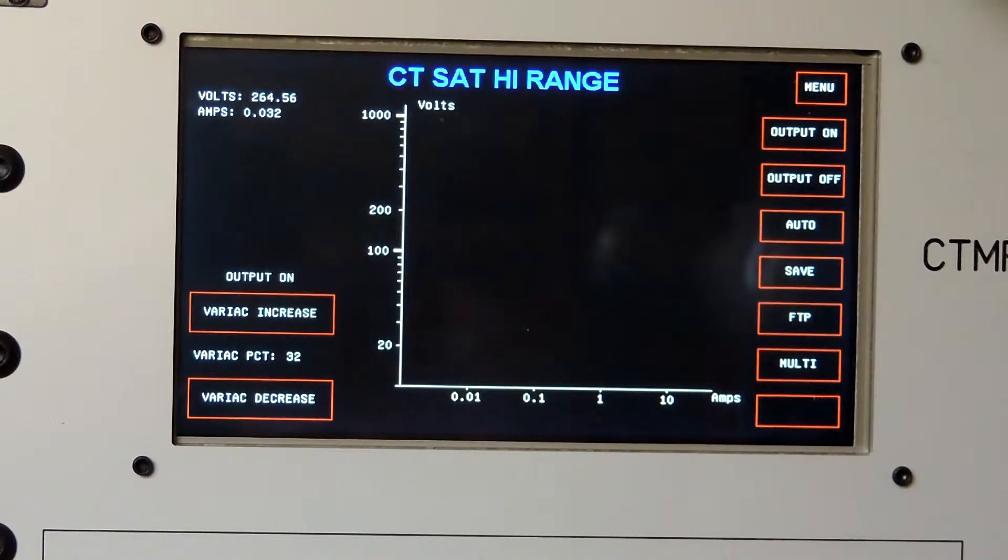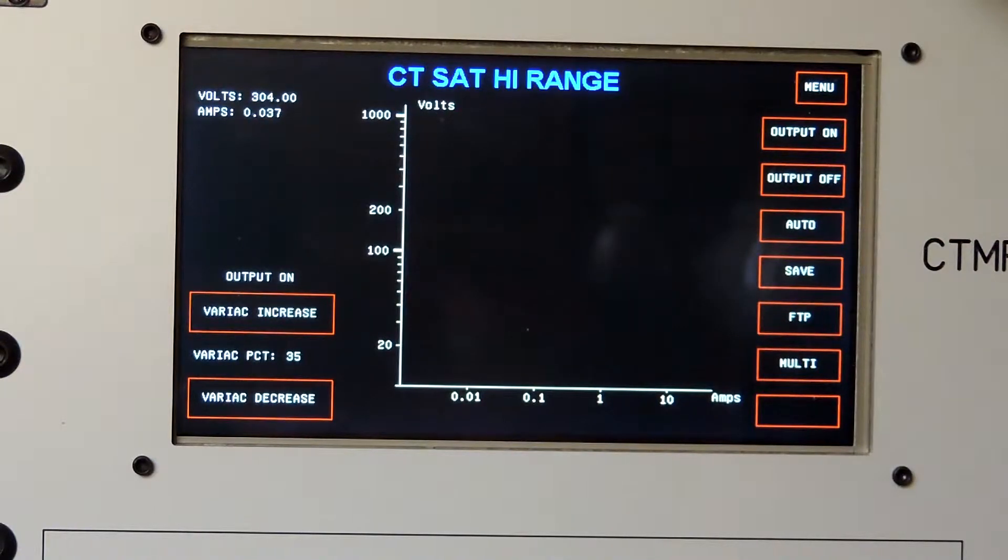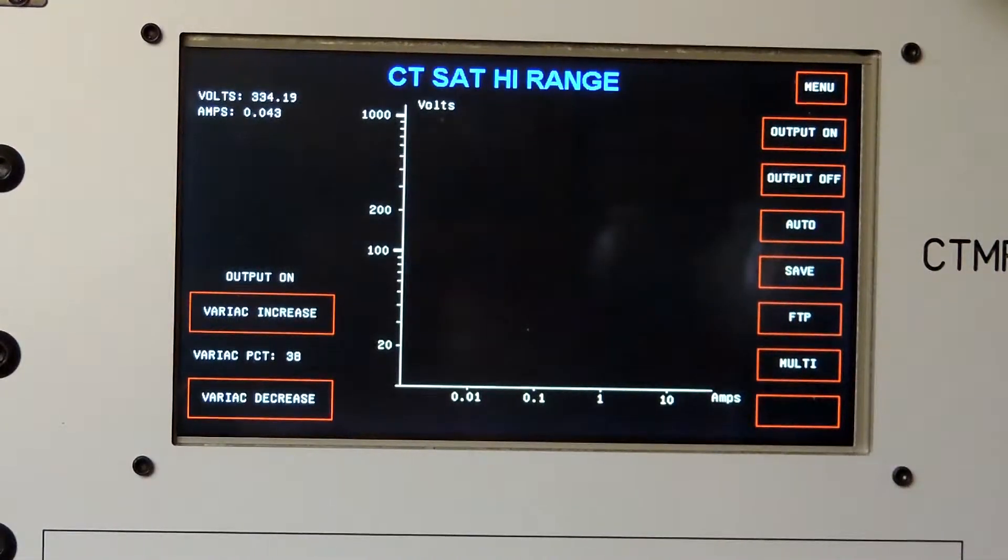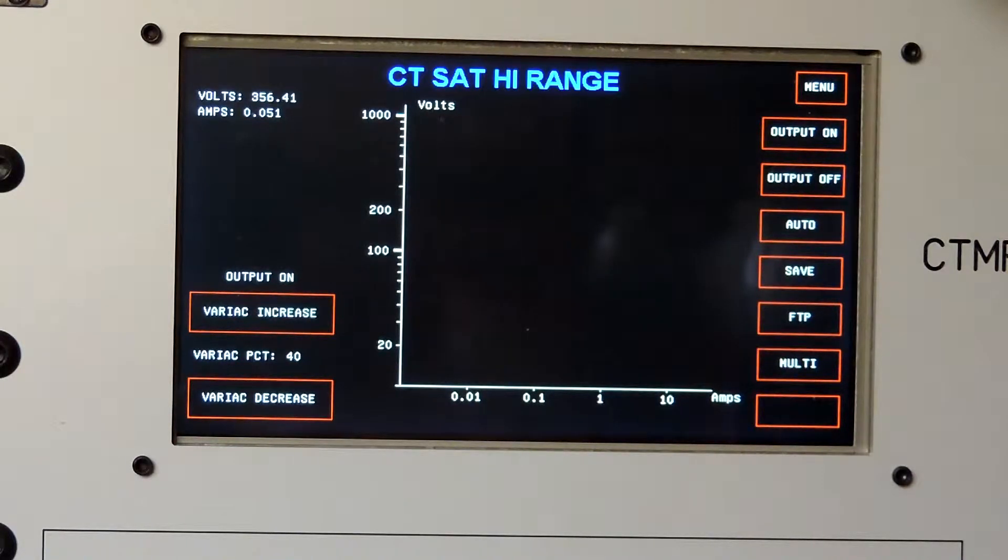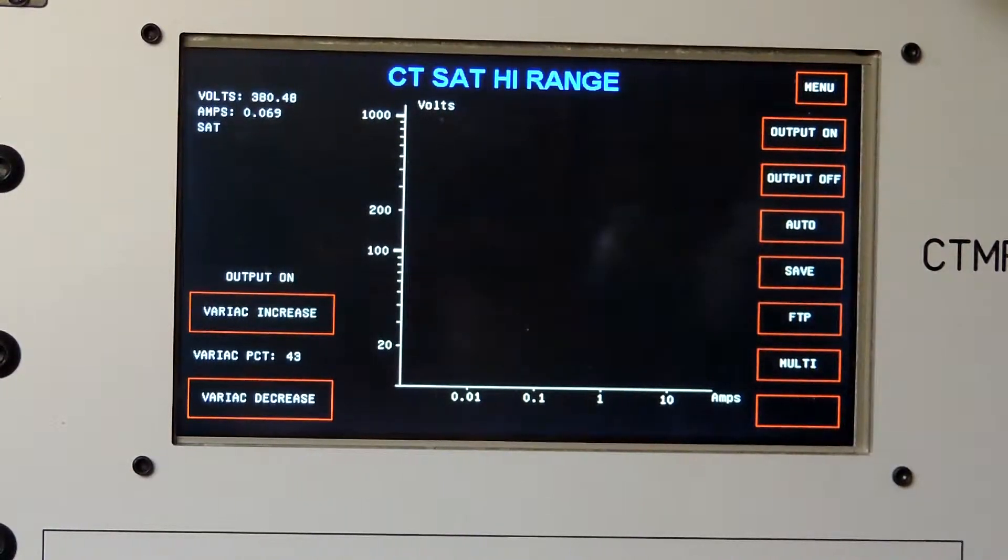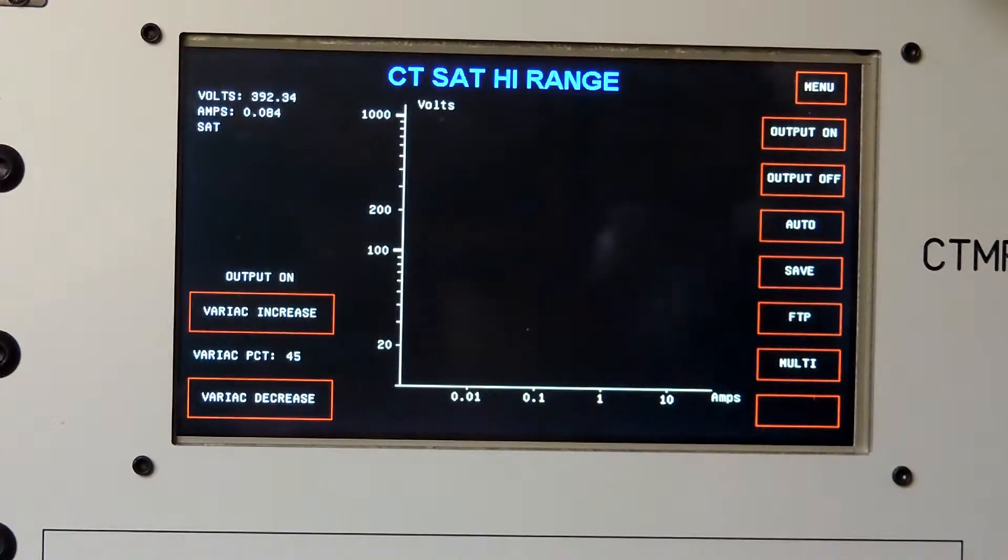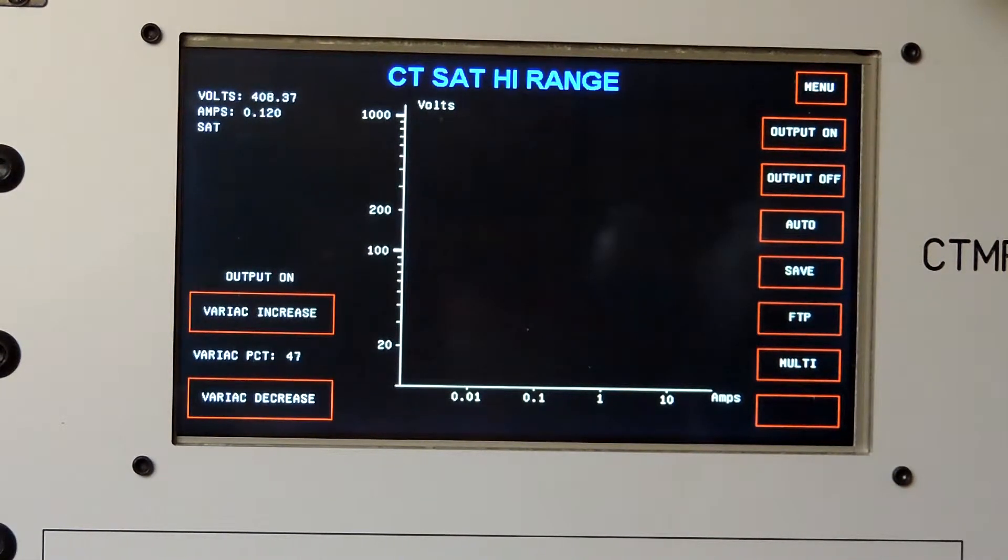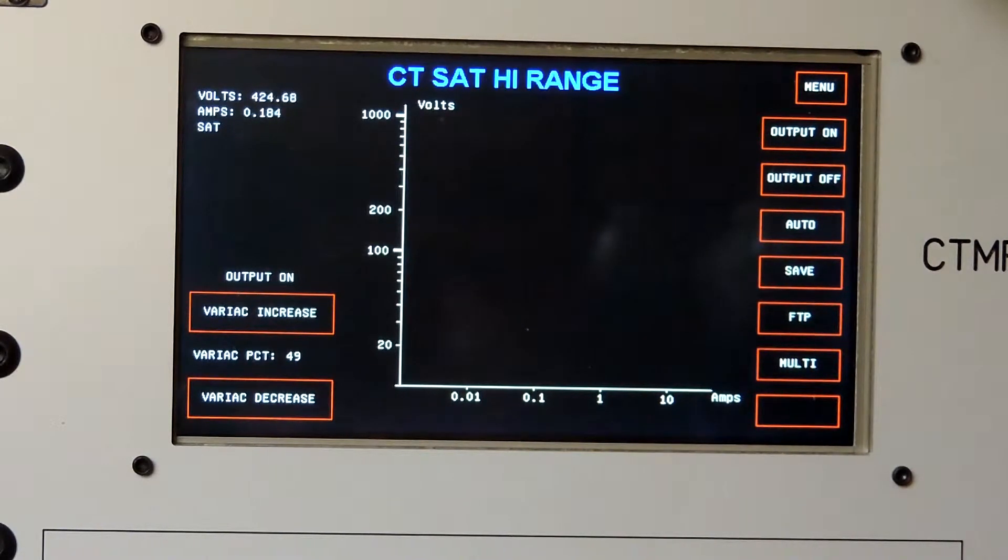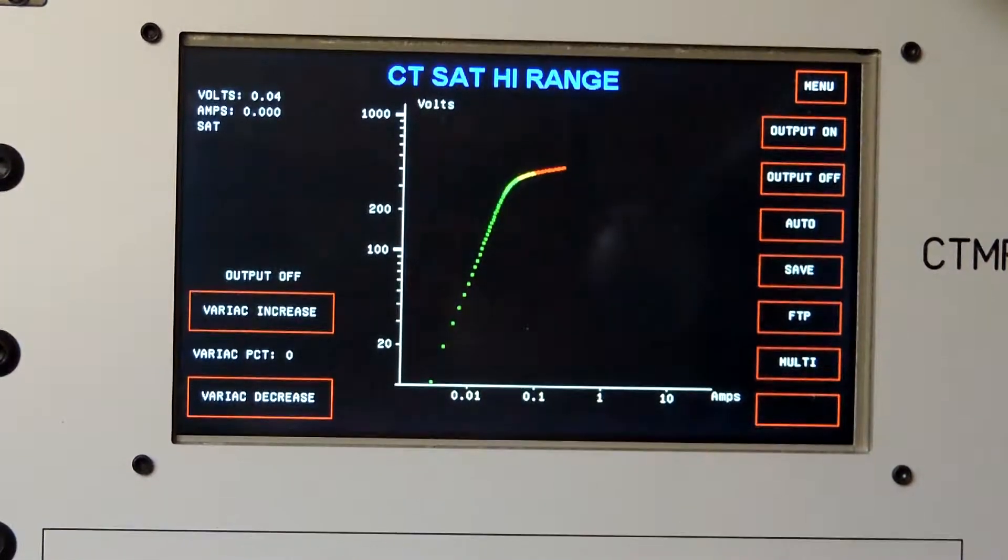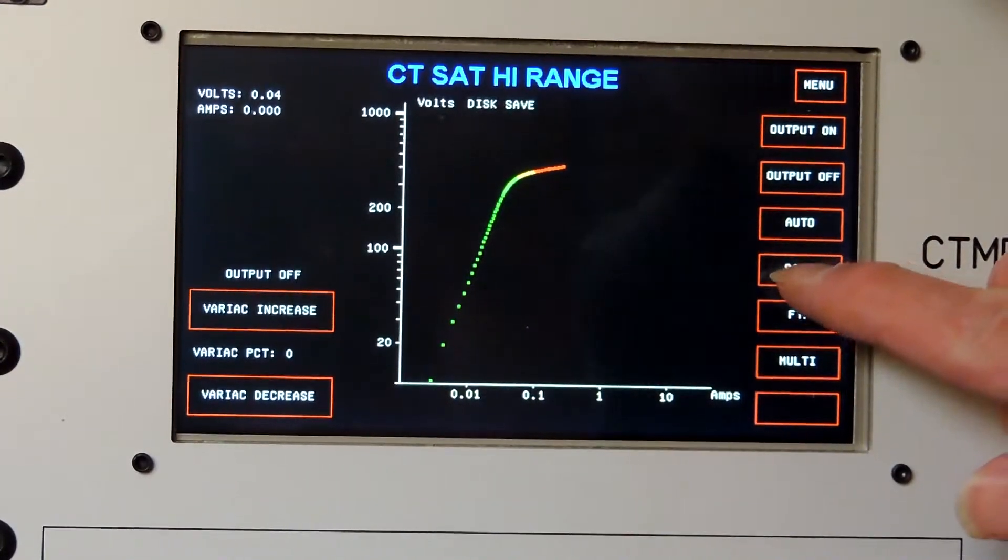There's no point doing a manual saturation test, so it's much better to do it this way. It is now raising the voltage and taking voltage and current data. The distortion algorithm determines when it's saturated, and it will say SAT under the amps. There it says that now, so it has reached the saturation point. You can hear it humming a little bit as it drives it deeper into saturation. It has now plotted the curve, so it has acquired the saturation data.